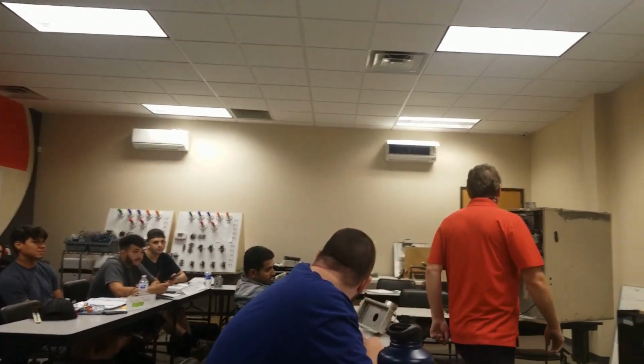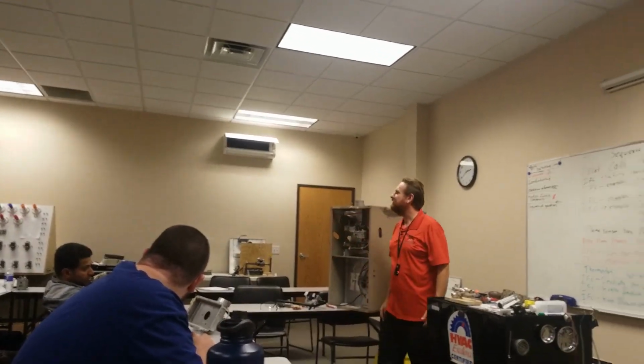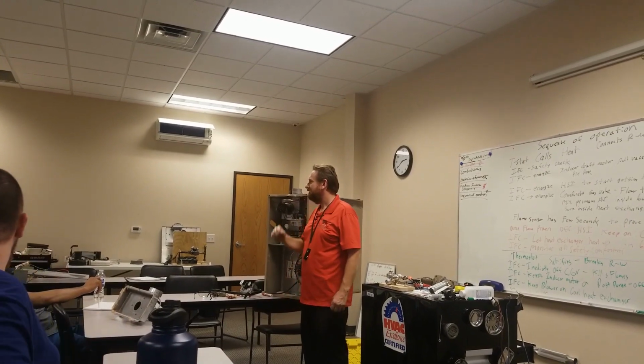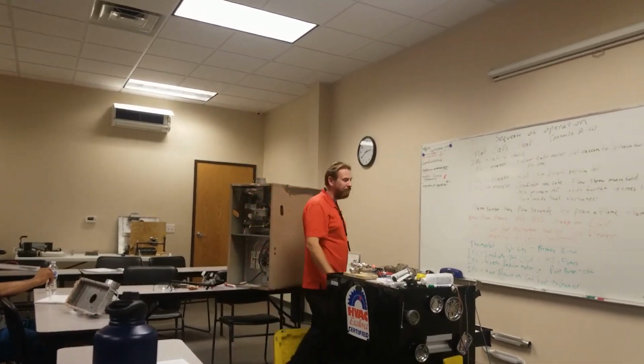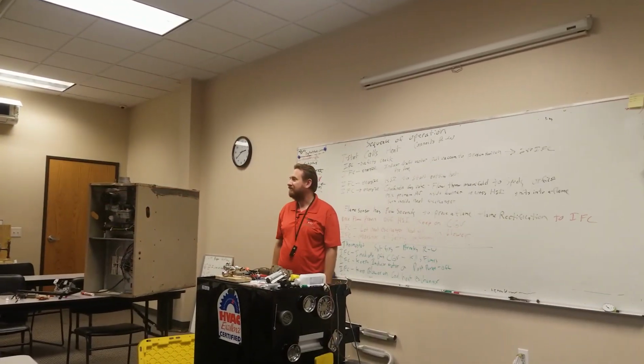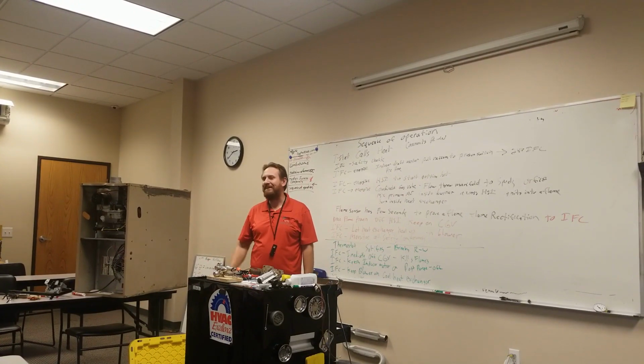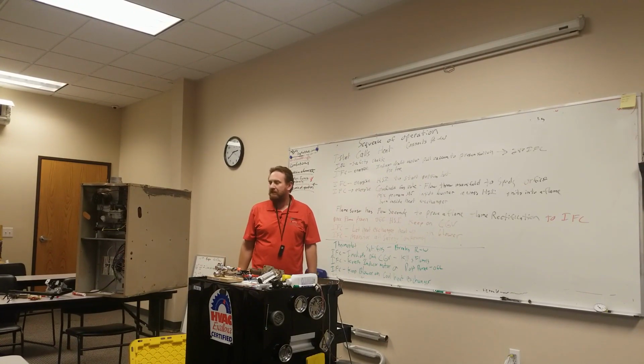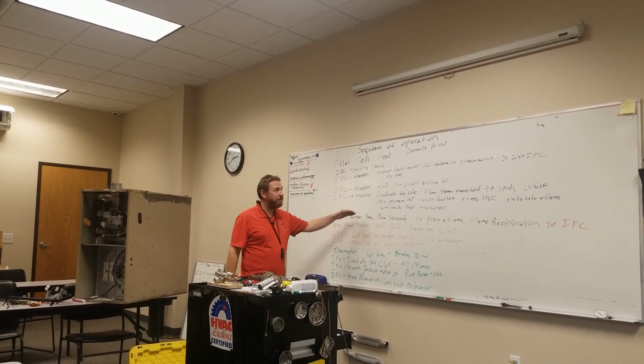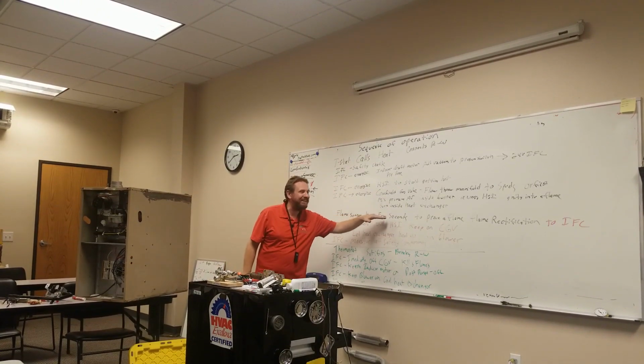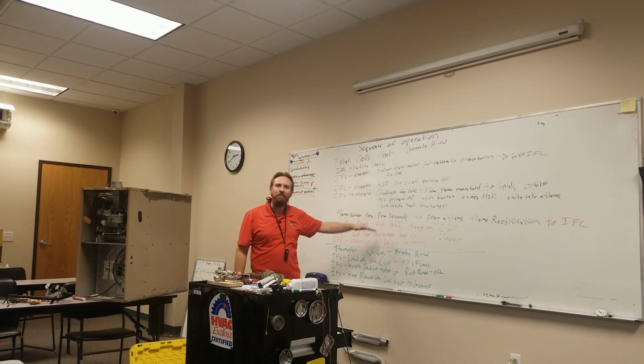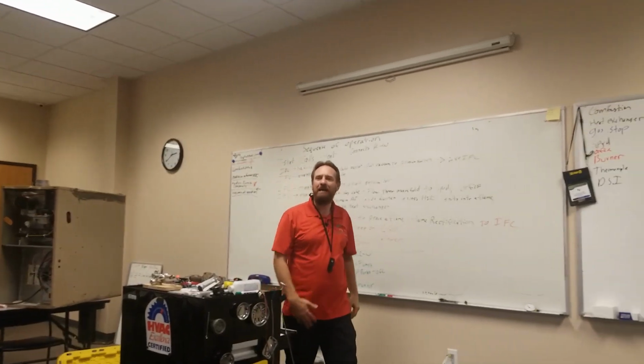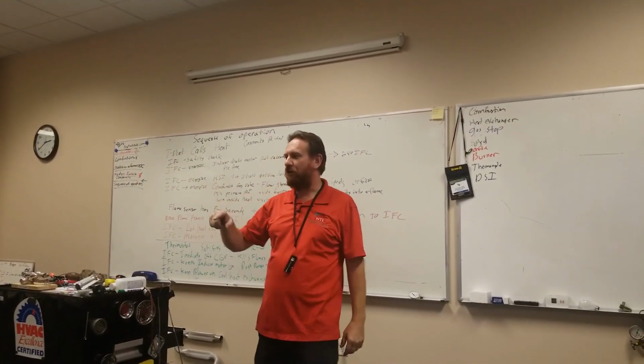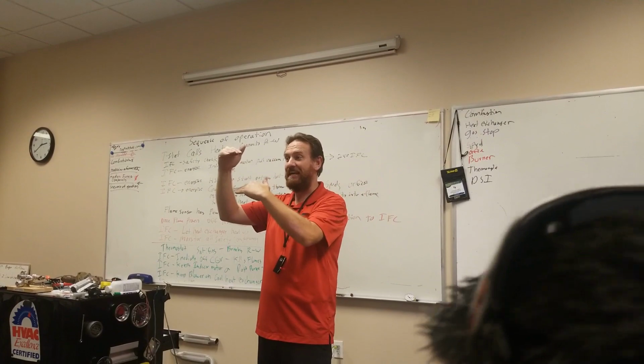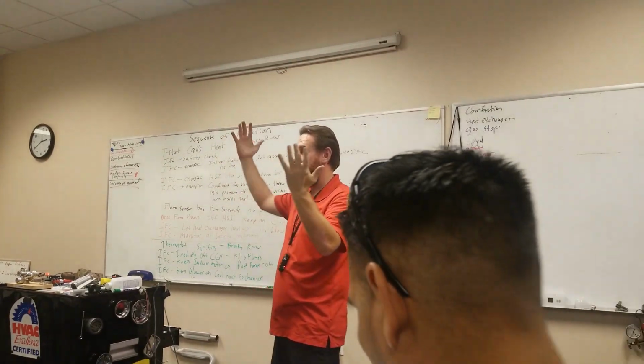Jason, how important is that? How often does that happen, what you just described right there? All the time. Number 1 call for gas heat, dirty flame sensor. Number 1 gas heat call. Number 2 gas heat call, dirty filter. That right there happens. You can see the flame, and in a few seconds it shut off. See how the sequence of operation helps you diagnose what's happening? Go through the little checklist. Oh, well, but this happened and it didn't happen. Well, what's between those two?